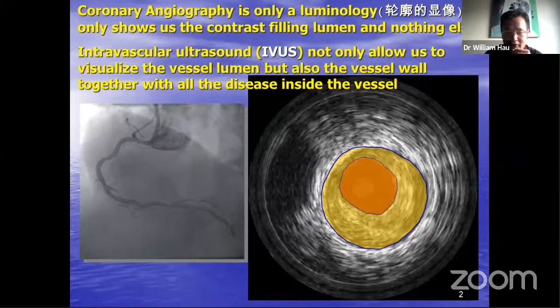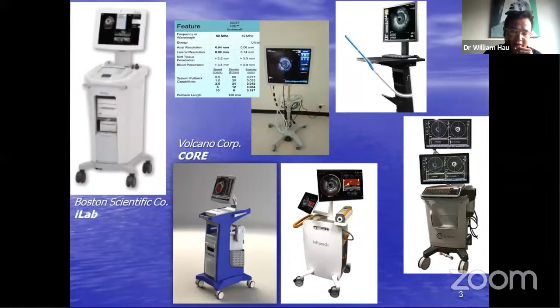than coronary angiography. Right now in the market, we have a couple of companies with IVUS technology. We have the iLab from Boston Scientific. This machine can do both the 40 megahertz IVUS catheter and the 60 megahertz IVUS catheter. And we have the Philips Volcano with the core machine. This machine can do the solid state IVUS catheter and the mechanical IVUS catheter. And we also have the HD IVUS from ACIST. This machine can do dual frequency on one single catheter, with the 40 megahertz and 60 megahertz transducer on the same catheter.